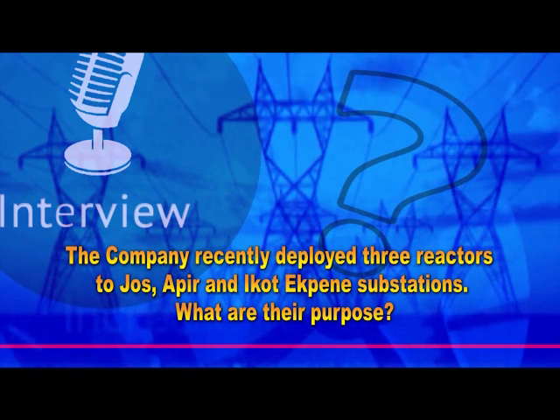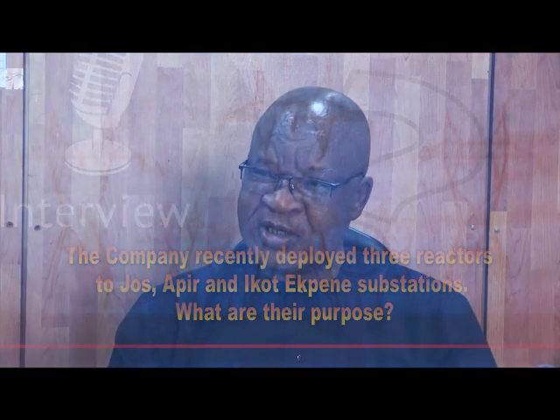The company recently deployed 3 reactors to Jos, Apir and Ikot Ekpene substations. What are their purposes? TCN is sandwiched between the distribution sector and the generation sector. We only convey energy from the power stations to the distribution sector. So anytime the generators are running and the DISCOs are not utilizing the energy, it creates overvoltage on our transmission lines and substations.